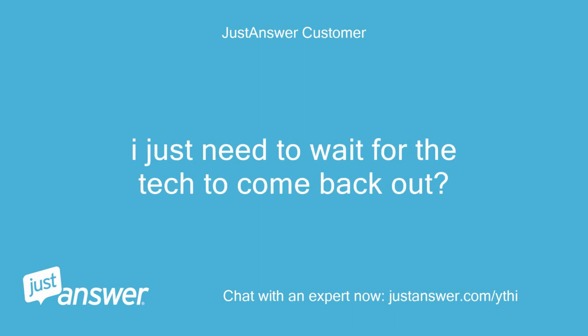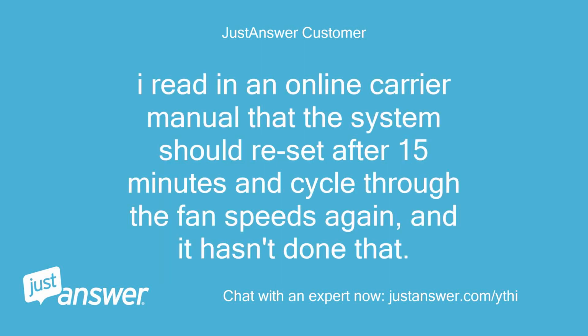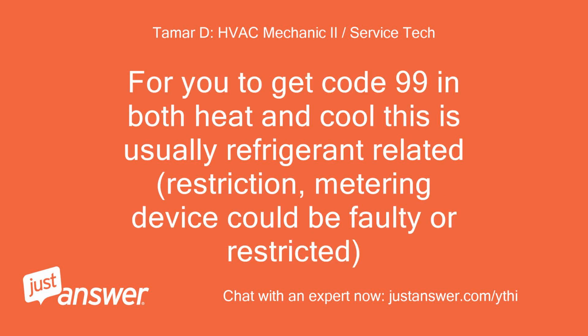I just need to wait for the tech to come back out? Nothing to do now? I read in an online Carrier manual that the system should reset after 15 minutes and cycle through the fan speeds again, and it hasn't done that. That's what it sounds like. After you get code 99, it may lock itself out for some time before it will try again. For you to get code 99 in both heat and cool, this is usually refrigerant related. Restriction, metering device could be faulty or restricted.